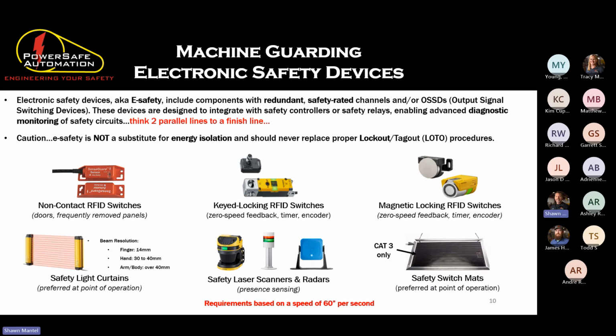Well, the problem with safety laser scanners and switch mats with saying 3 foot is enough is I can put my toes outside those zones, lean over the machine and hold on to the machine while I use my other hand to adjust it and then push myself back up. And because they're 2D planes, the machine won't trip because the scanner won't see it. Safety radar is a newer product out there that looks at a 3D area. So it's a 3D version of a laser scanner. That's going to be a lot harder to defeat because of the 3D plane instead of just a 2D plane with the scanners and the safety mats.